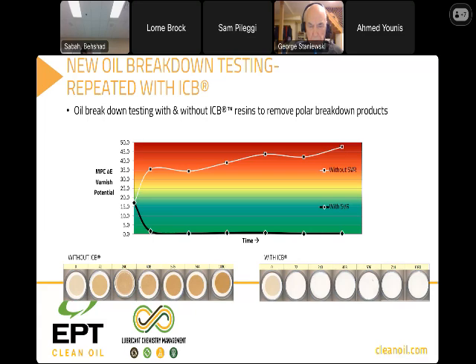No acid. The condemning limit for lubricants right now is the combination of low additive, under 25%, in combination with high acid number. So we can still get this situation with low additive, but you're never going to have an acid number, and you're never going to have a varnish potential.